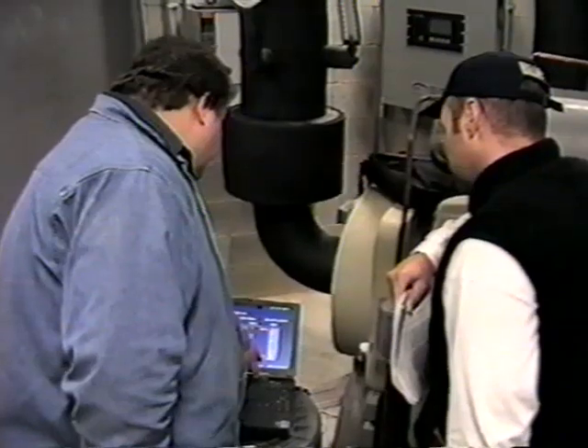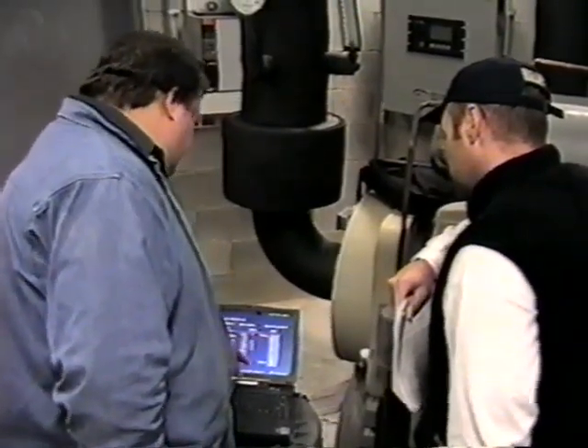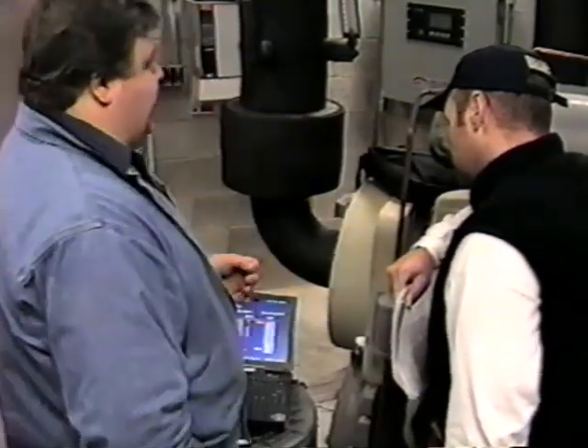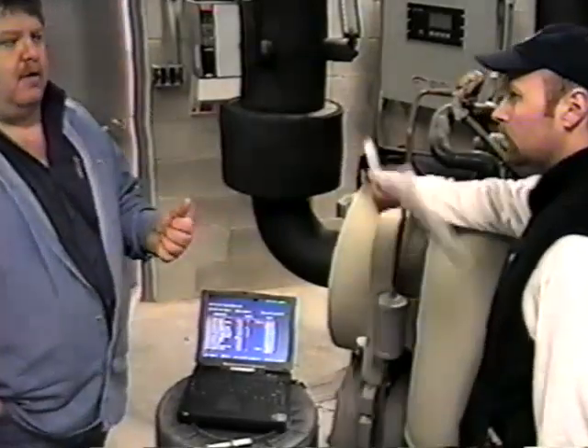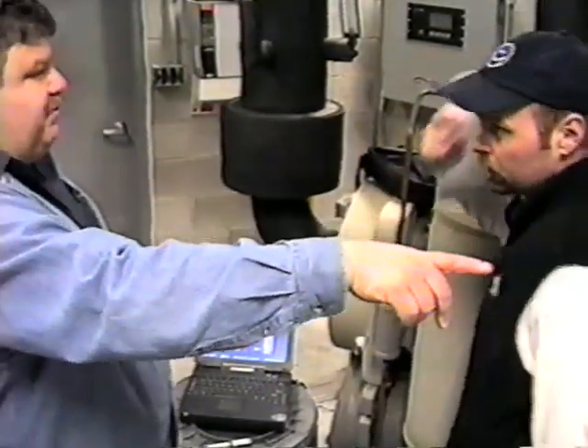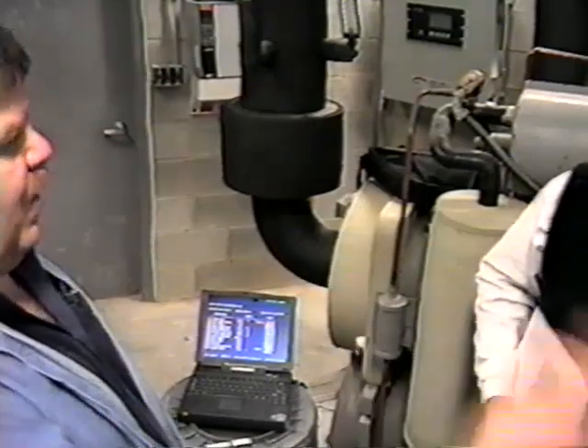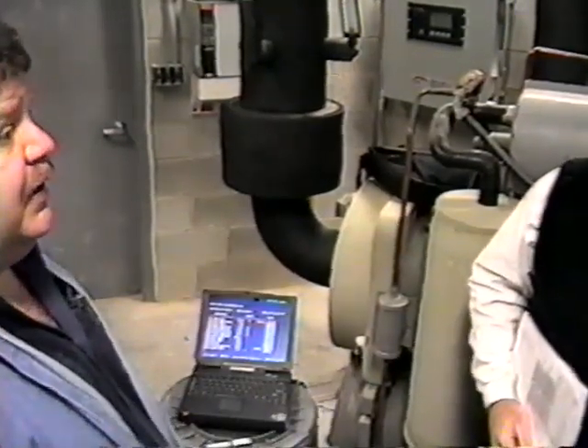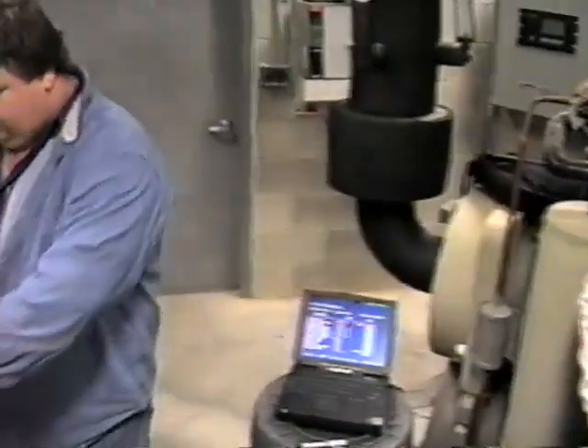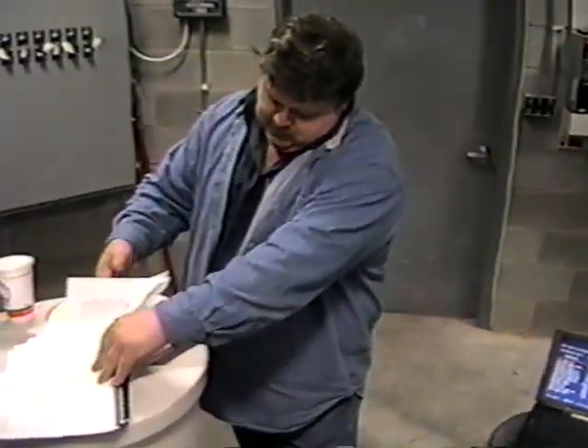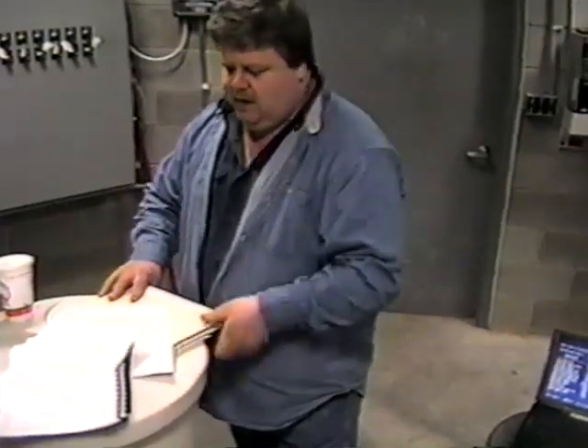And if you see things where this one says control on it, what's happened is this underfloor heat pump has an inhibit on it. Because this condenser water temperature is so critical, we don't want it to get below, let's say, 70 degrees. The control point for it was, was it 90? Yeah, wherever I wrote it down, it was 90, I believe. Anyhow, we don't want that to stay below 70 for any prolonged period, or it causes problems with the thing running, it'll trip.